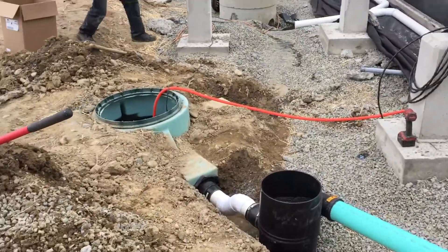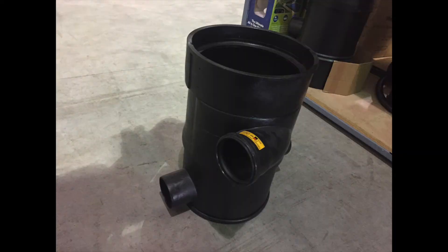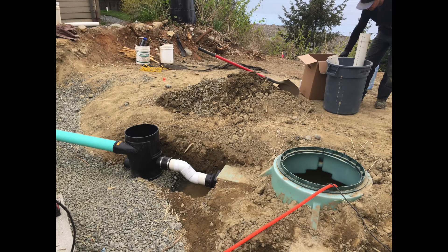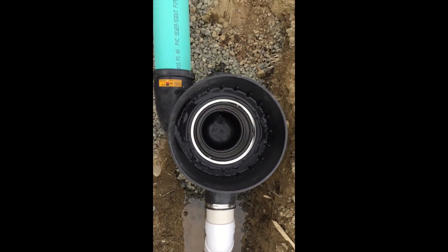The vortex filter makes sure that the water that goes into our storage system is clean. It's a vortex filter — the top horizontal line is the inlet, and you can see the water enters on the side and swirls around. There's a metal strainer basket inside which filters the leaves and pine cones out. The debris goes out the bottom and the clean water goes out the white line and into the transfer tank. It's really quite clever — you'll see the water swirling in a moment.